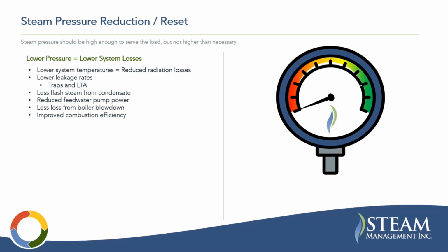So you reduce radiation losses, and you reduce the force to drive flow through leak points like traps or any leaks to atmosphere. Now you have less upstream pressure to push steam out of those holes. There's also going to be less flash steam from a higher pressure condensate, because your condensate is now coming out at a lower temperature. So you're going to mitigate flash steam a little bit.